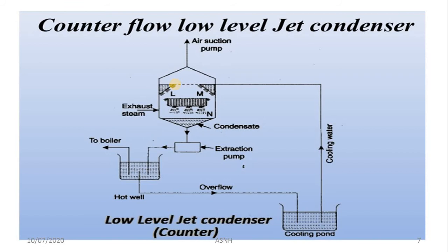Now there are two types of condenser. Again, that particular condenser is not mentioned in this slide, but it is the same as the counter flow, only that particular line, that is the condensate line, is longer, and the water directly enters the hot well in the absence of a condensate extraction pump. So the first type is the parallel flow jet condenser, the second one is the counter flow jet condenser. Both come under the low level jet condenser.